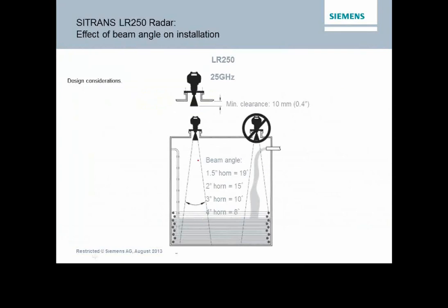And that also gives you an example of why you might want to go to a larger process connection, even though you have space available for a smaller unit, just to get a tighter beam and more accurate measurement with less distraction of what might be obstructions in the tank.